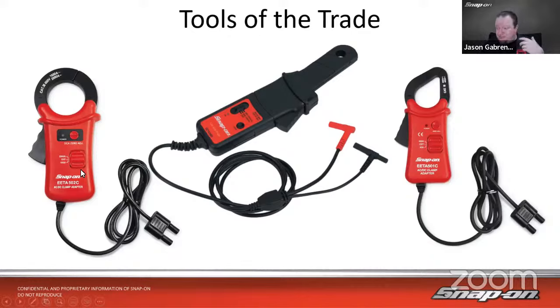Now, that being said, with our scopes, if you're using this probe in the middle here, that would be on your low amp probe setting, and you just set it up for a low amp probe and you're good to go. On the other two, since they're technically designed for a meter, not for the scope, I mean, they'll work, but that's not what they're designed for.